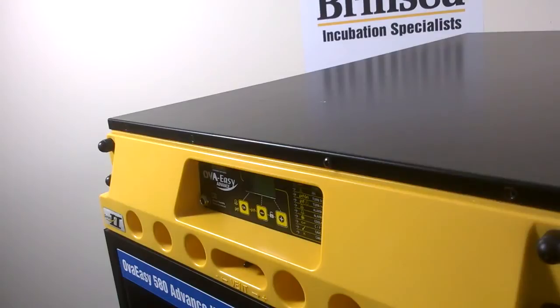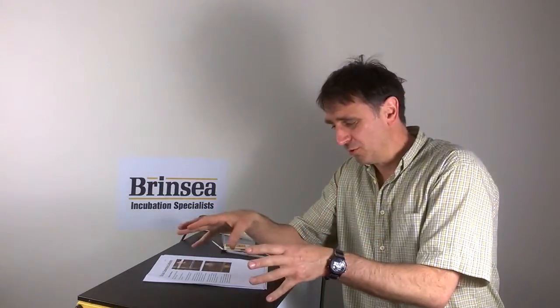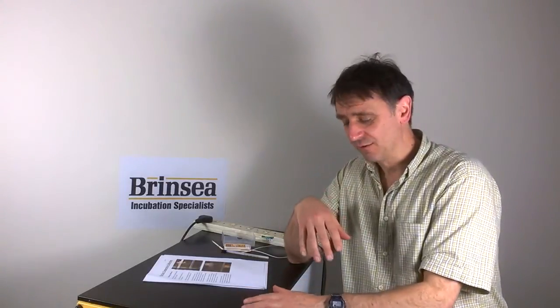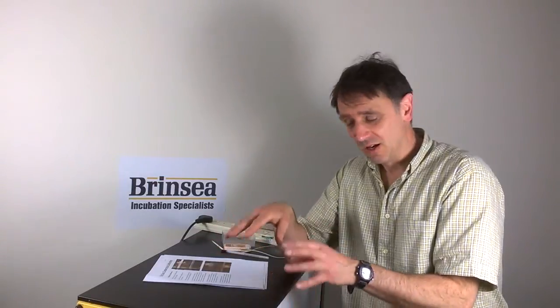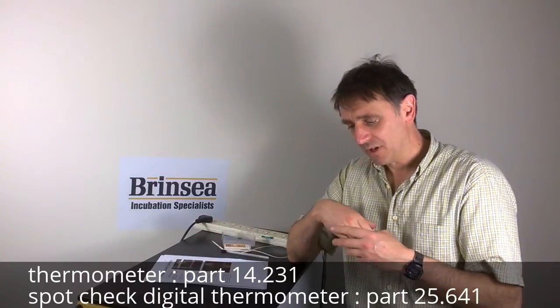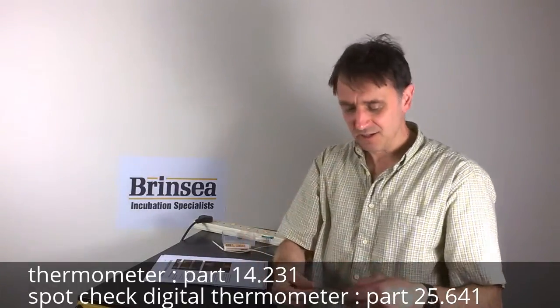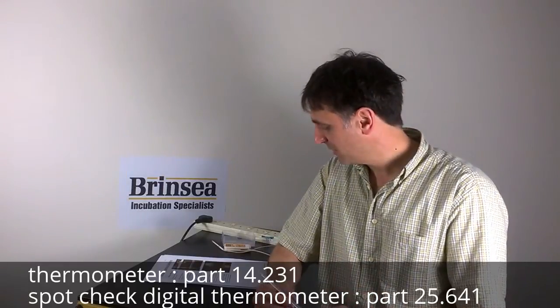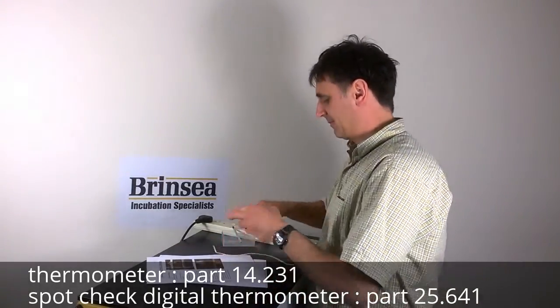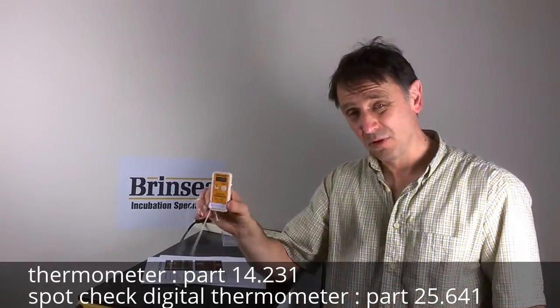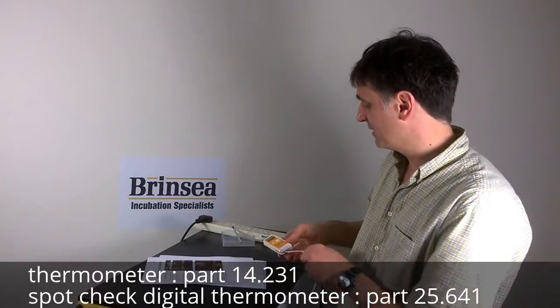So let's assume I've done all that. What we now need to show you is how to calibrate this machine. So once we've fitted the OVAEASY Series II control module, the replacement module, what we need to do is to turn our OVAEASY machine back on, which is what I've done with this machine. And then we need to follow a simple process for recalibrating the OVAEASY machine. And that involves using a thermometer. So it may be the glass thermometer that we've already described, this glass thermometer for calibration, or it may be using one of these spot check digital thermometers, which is an alternative way of checking the calibration.